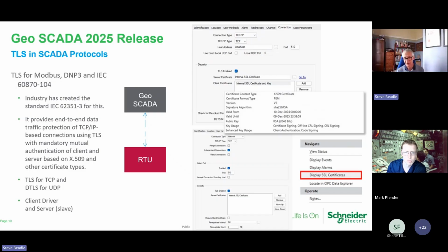In our implementation of TLS, we've made this happen for the three major SCADA protocols. That's Modbus, DNP3, and IEC 60870. Note that we already do TLS authentication for IEC 61850, that's the IED standard, for OPC UA, and for MQTT. So those are already covered. So this covers the rest, effectively, the rest of the bulk of SCADA protocols.